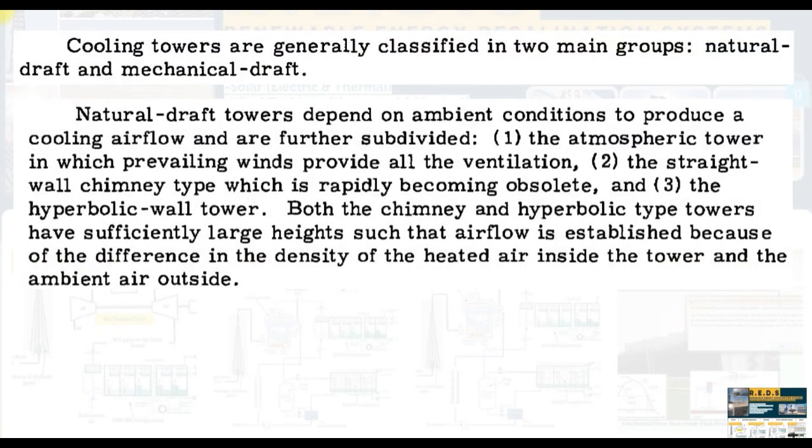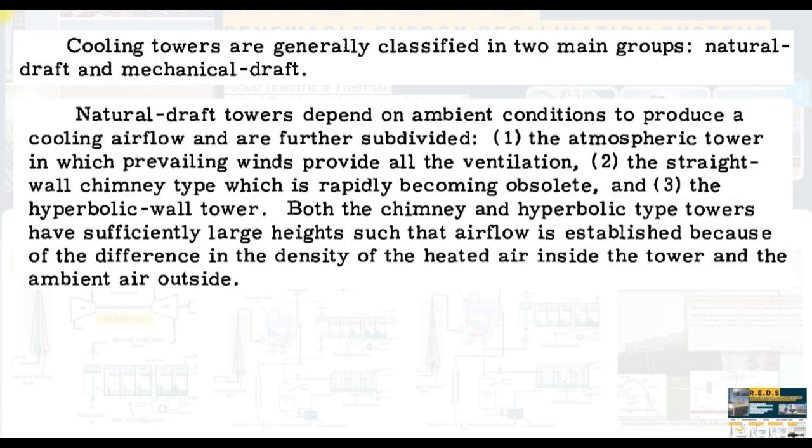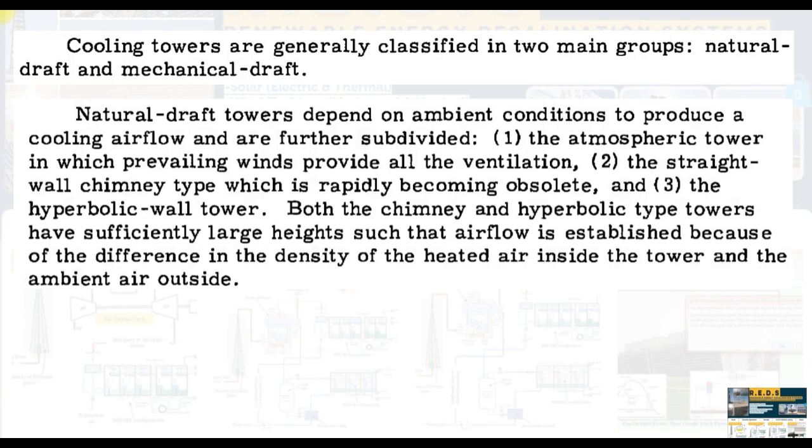Cooling towers are generally classified into two main groups: Natural draft that we are going to talk about today and mechanical draft which can use large fans. Natural draft towers depend on ambient conditions to produce cooling flow and are further subdivided into the atmospheric tower in which prevailing winds provide all ventilation, the straight wall chimney type which has rapidly become obsolete, and the hyperbolic wall tower.